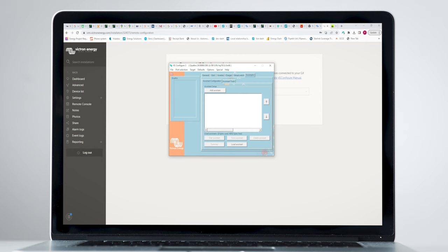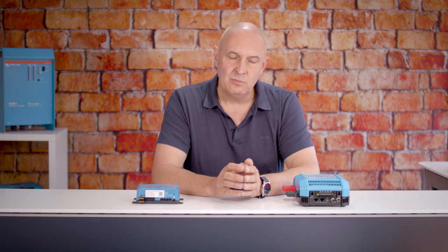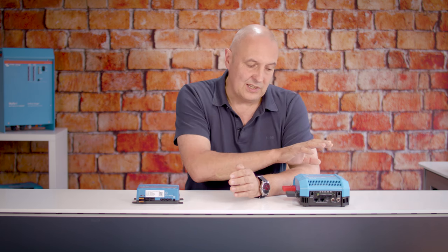The whole installation is made much more straightforward, and really just to recover the point that was made earlier, the only thing that might look slightly anomalous is that you could have set a charging voltage using VE Configure that is effectively overridden by DVCC, and that might just be a little bit confusing, but that's the nature of the way that DVCC works. So hopefully I've conveyed how simple it is to configure a system with Victron Smart Lithium batteries using the Lynx Smart BMS, and how it's taken an awful lot of the configuration requirements out of the Quattro or MultiPlus, and that you now have a good idea of how that will all look if you're interrogating the system and understand why things might vary slightly from what you think you've set because of DVCC overwriting values.